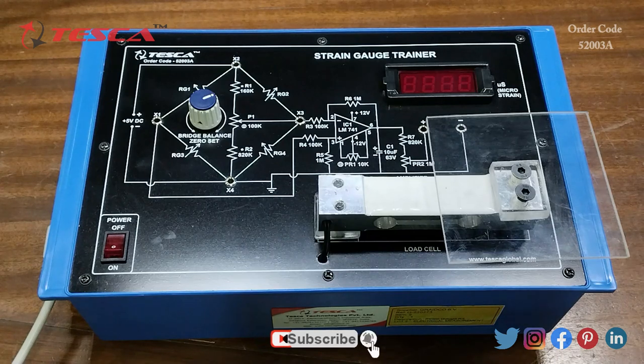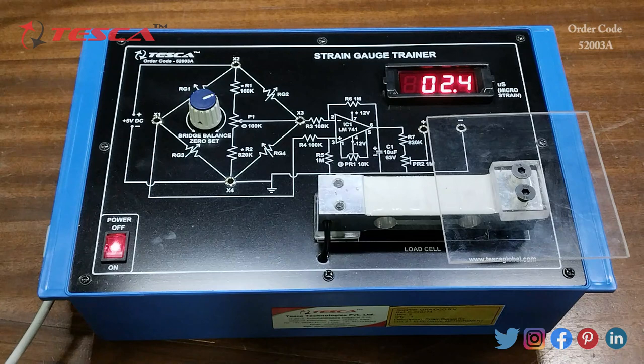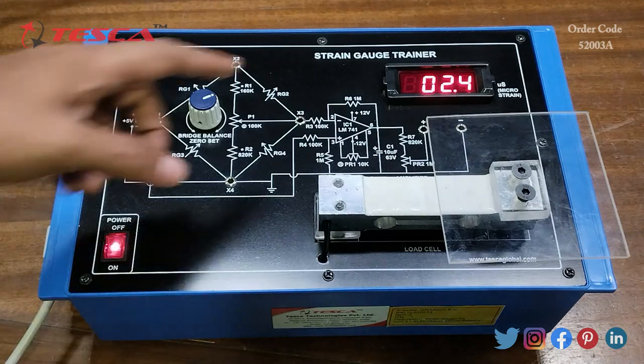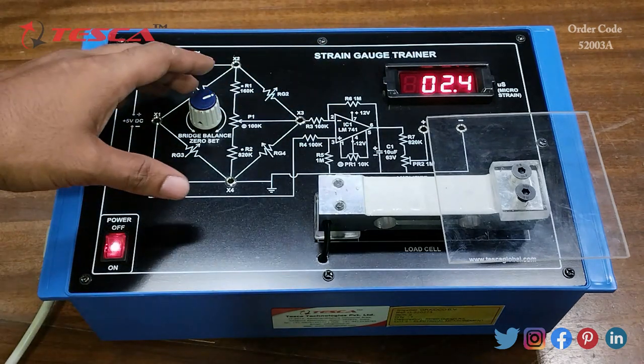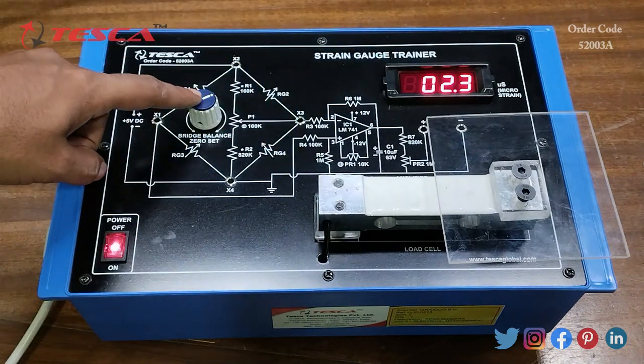Now we are going to perform an experiment on the kit. The experiment is to study strain measurement using strain gauges and a cantilever assembly. First, we will connect this kit with the main supply by connecting a mains cord in the three-pin section. Now we will switch on the kit. Here you can see that the display is showing 2.4, so we have to set it to zero before performing the experiment. We can set it to zero using this bridge balance zero set pot.